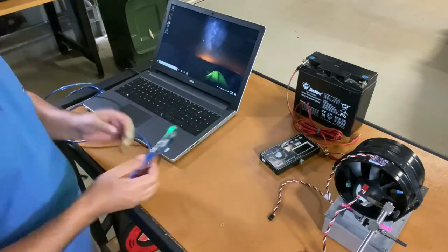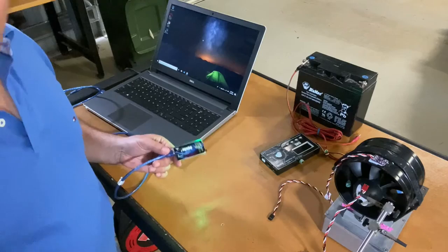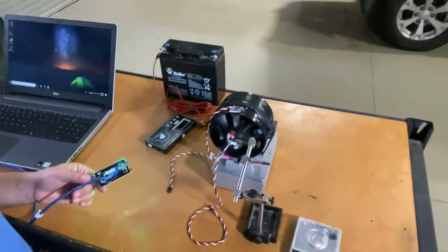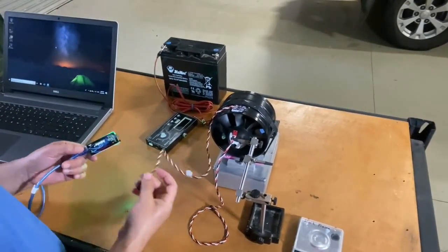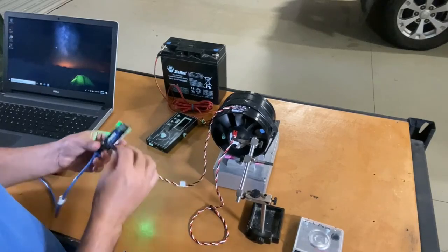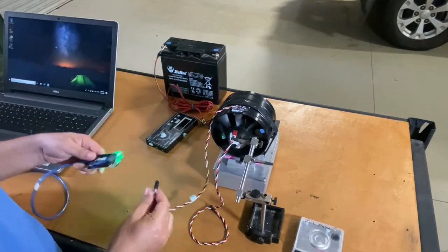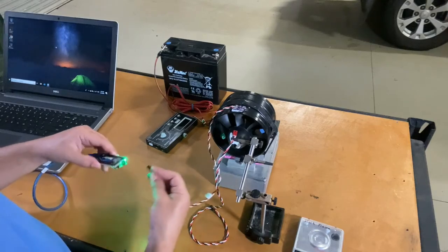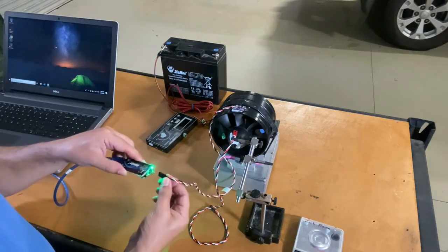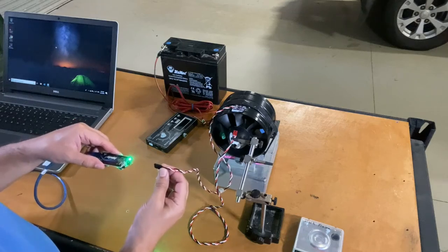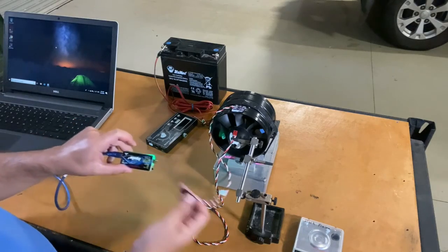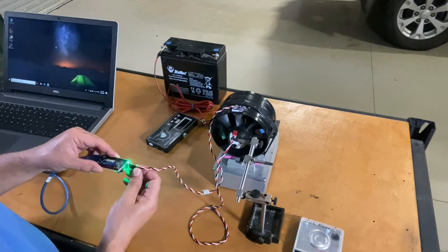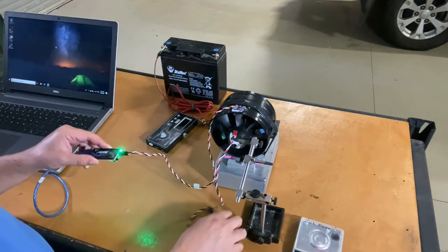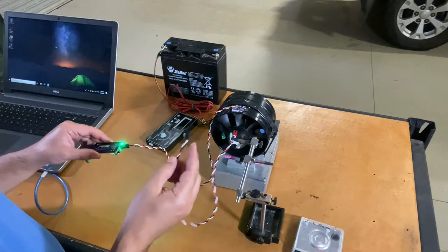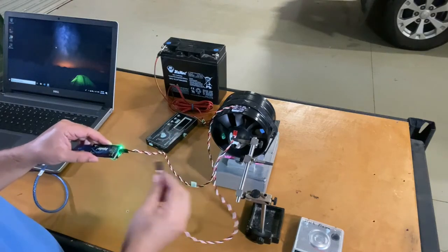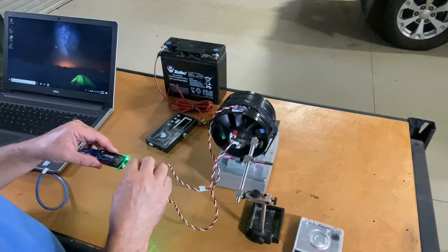So once that is done, now you want to connect up the sensors. So I'll just rotate the camera. All right, so the accelerometer goes into accelerometer number 1, and that gets positioned like this. So the black lead faces the top label of the Impulse, so I'll plug that in. And for the infrared sensor, again, the black lead of that faces the top label.